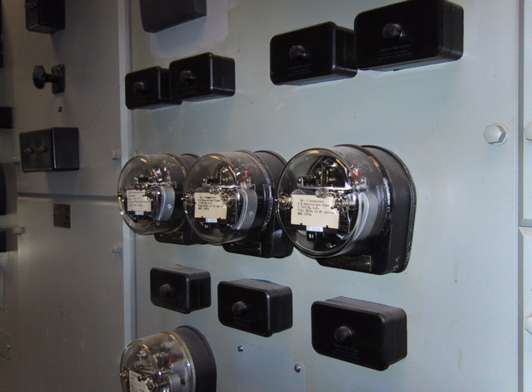If two or more coils are used, they must be at the same frequency, otherwise no net operating force is produced. These electromagnetic relays use the induction principle discovered by Galileo Ferraris in the late 19th century. The magnetic system in induction disk overcurrent relays is designed to detect overcurrents in a power system and operate with a predetermined time delay when certain overcurrent limits have been reached.